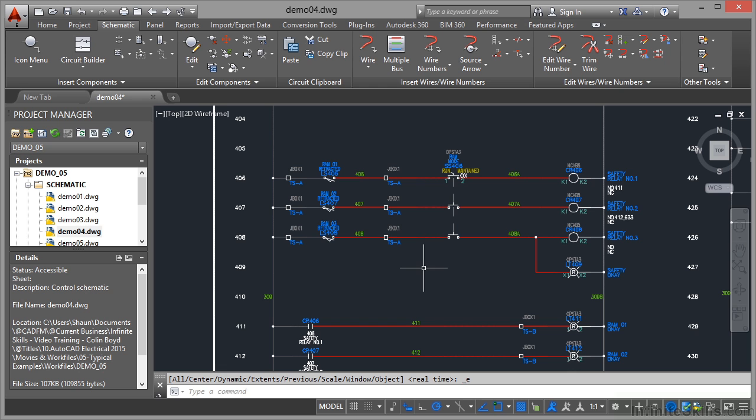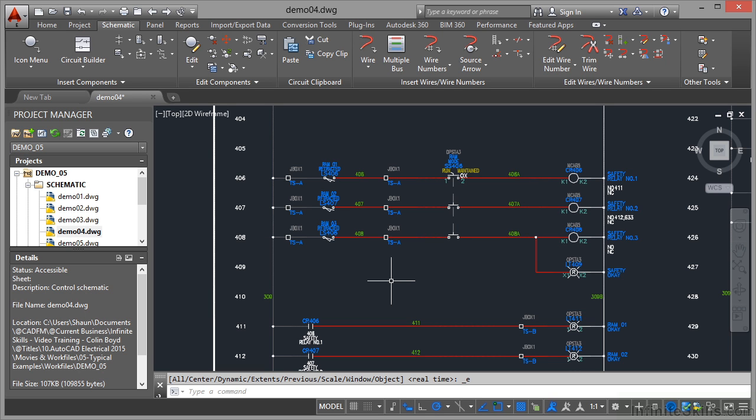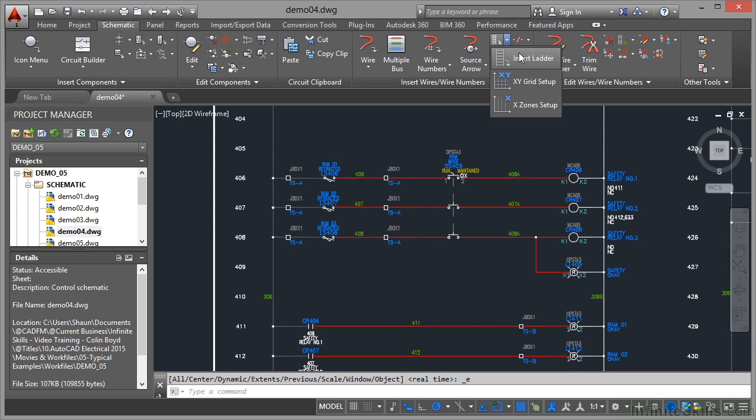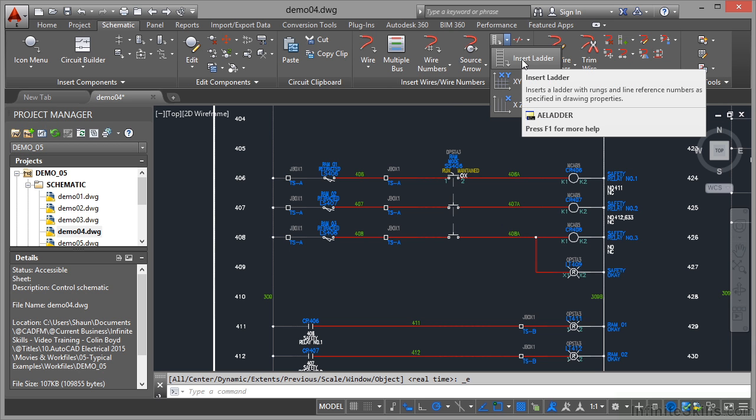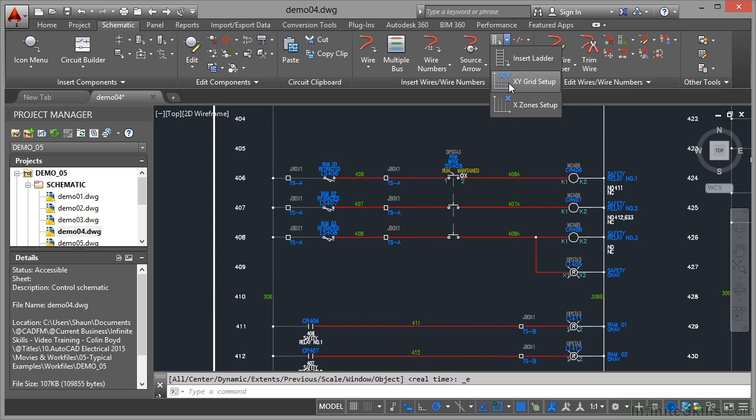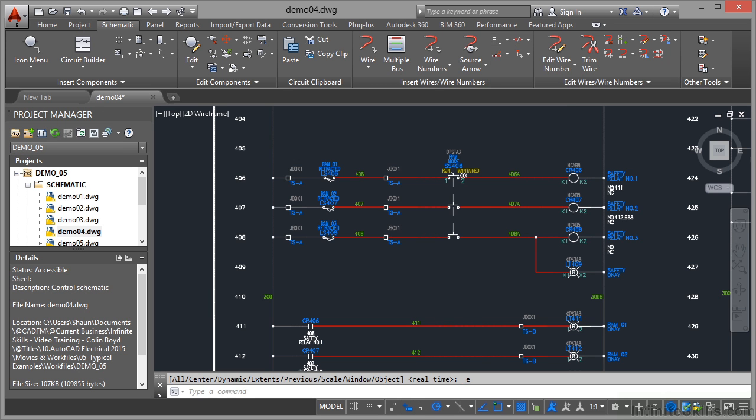Now something you'll notice are these numbers here: 406, 407, 408. They are the ladder rung numbers and you use this command here. If I click on the flyout there, I've got insert ladder, and what you do is you set up a special grid for ladders. You'll notice you've got XY grid setup and X zone setup. We'll cover those later, but those particular setups are important when you're setting up ladders in AutoCAD Electrical.